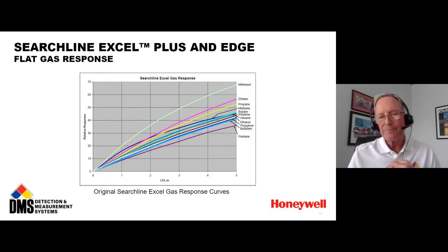Methanol, on the other hand, is the target gas in the calibration for which the previous Searchline Excel has the greatest response. That's why the curve is so high. But the point in bringing all this up is you see how wide the spread is between the pentane calibration and the methanol calibration and all of the gases in between. For those of you that are customers of ours for the Searchline Excel, one of our first questions is, what are your target gases? Because we wanted to make sure that we always supplied the right calibration for your application. I think this chart illustrates why that's important. You want to make sure you have the calibration that's appropriate for your application.